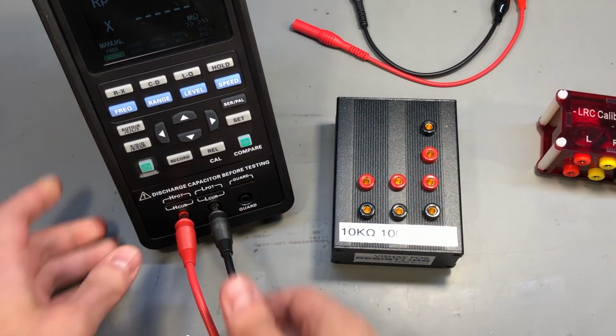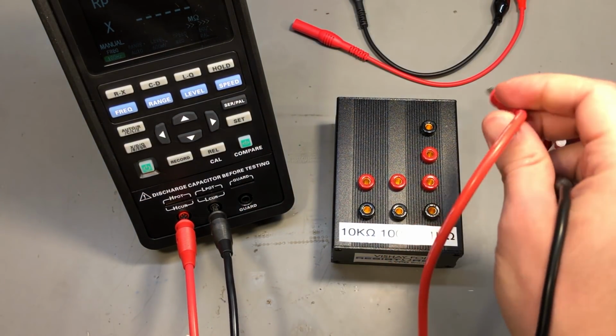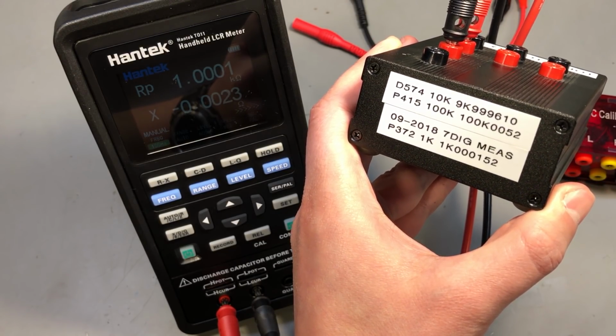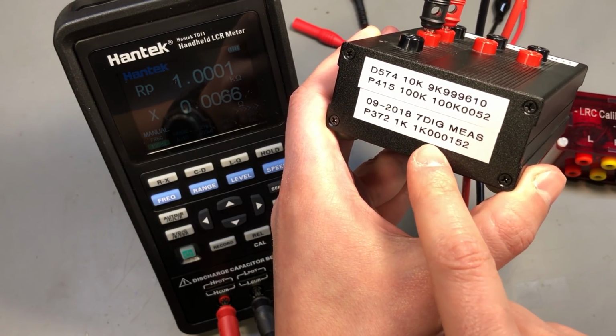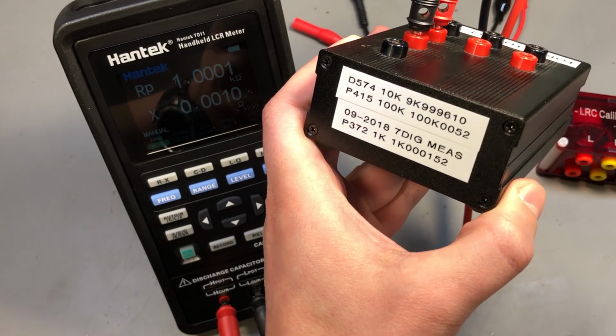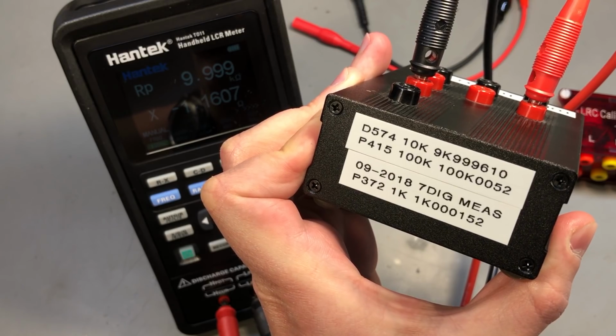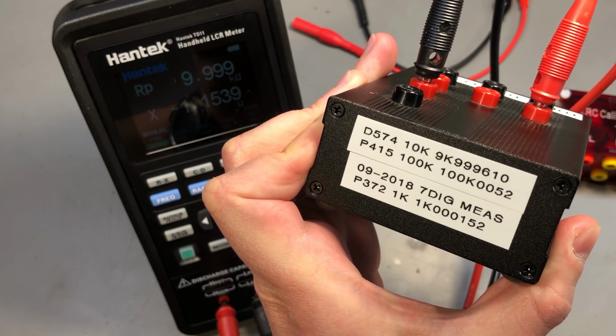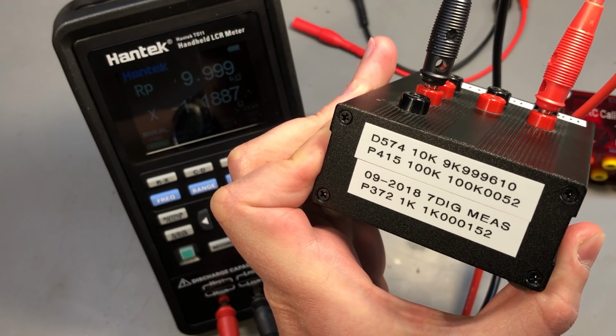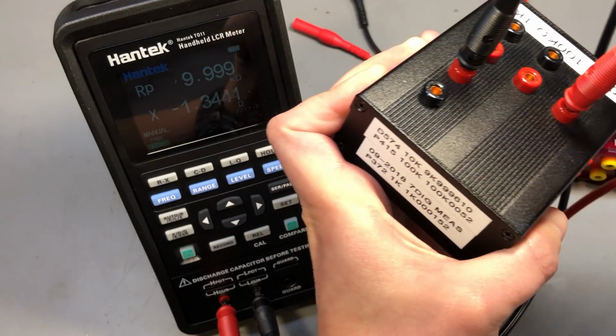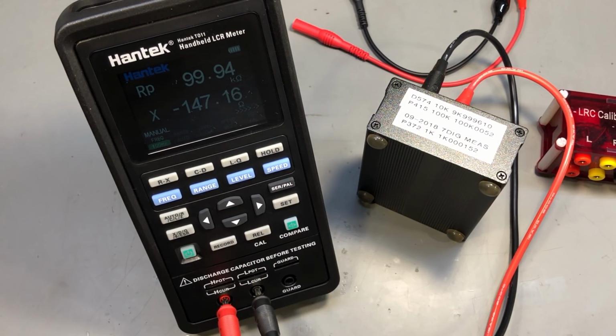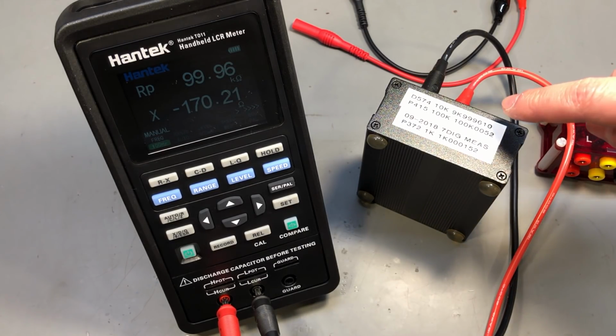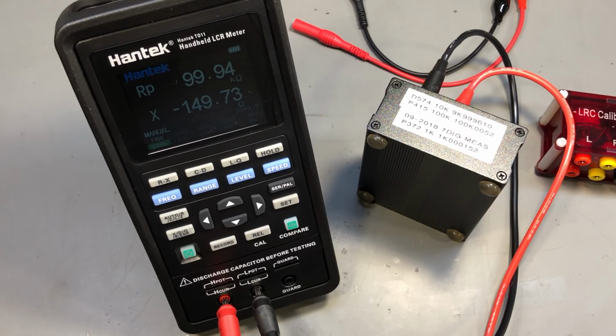Let's start by checking the 1K resistor. And it looks like the value measured for 1K is exactly what we expect to see. Let's try the 10K. For 10K, we are once again seeing exactly the value we are expecting on the LCR meter. Let's try the 100K. For 100K, we are 5 or 6 counts out from the measurement we are expected to see. But that is within the specified accuracy of the LCR meter, so no problem there.